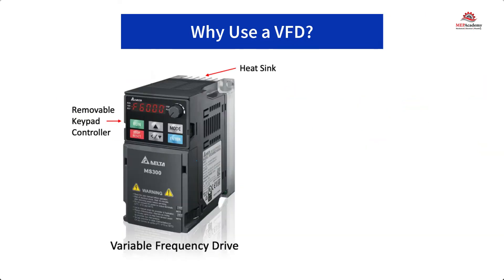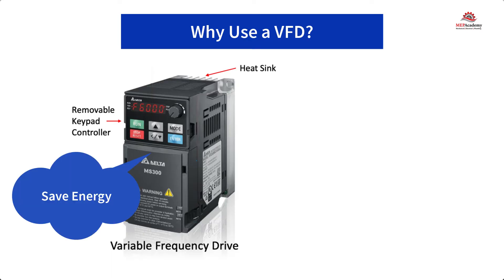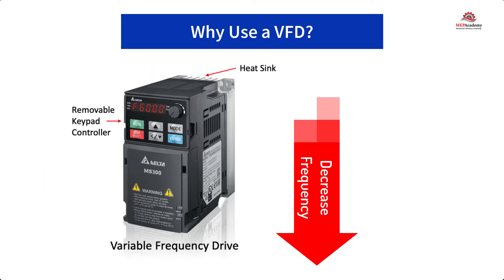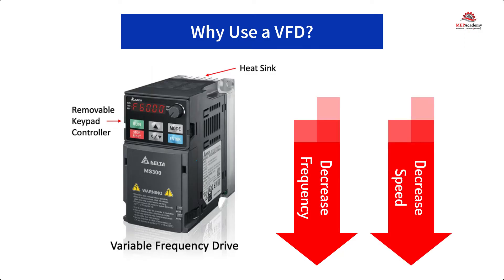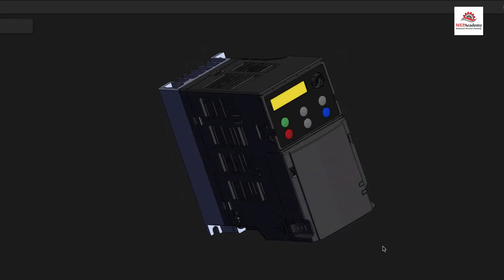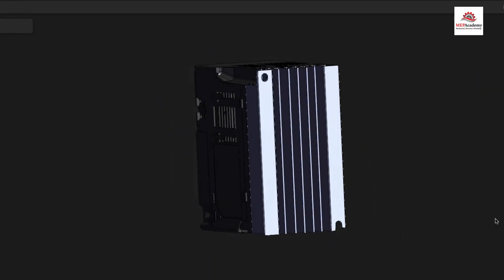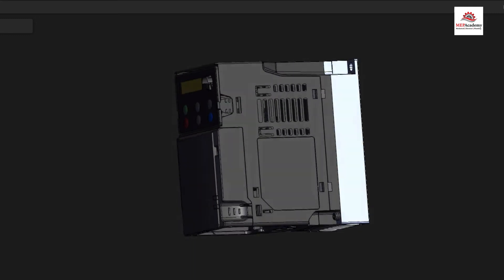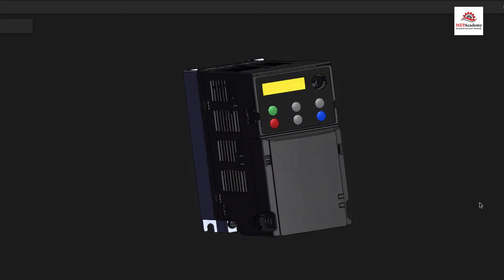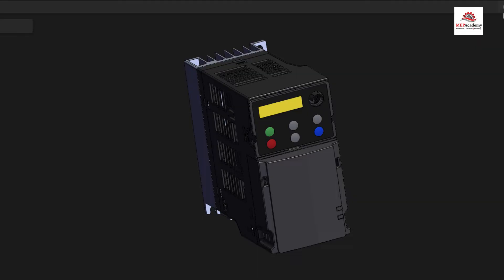So what is the purpose of a variable frequency drive? The main purpose is to vary the speed of a motor by varying its frequency and voltage to provide for energy savings. By increasing the frequency, you can increase the speed of the motor, and by decreasing the frequency, you can decrease the speed of the motor — it's basically that simple. Many of the existing motors that control mechanical equipment were originally designed to run at constant speed, which isn't energy efficient. These older motors were either in the on or off position and used some sort of artificial resistance to control flow.